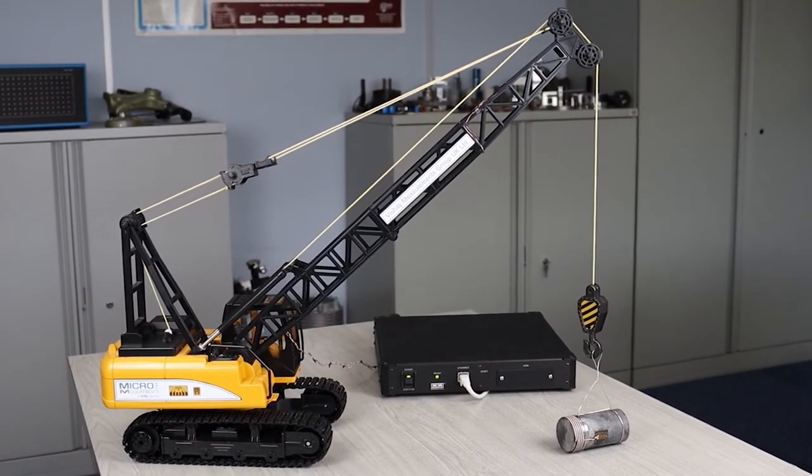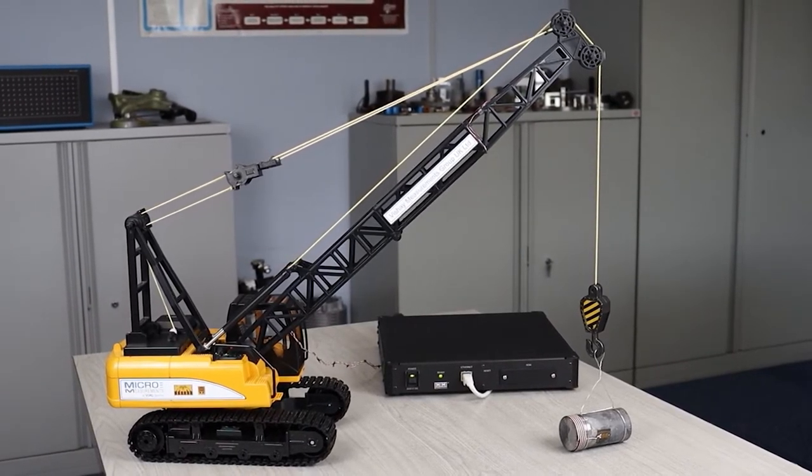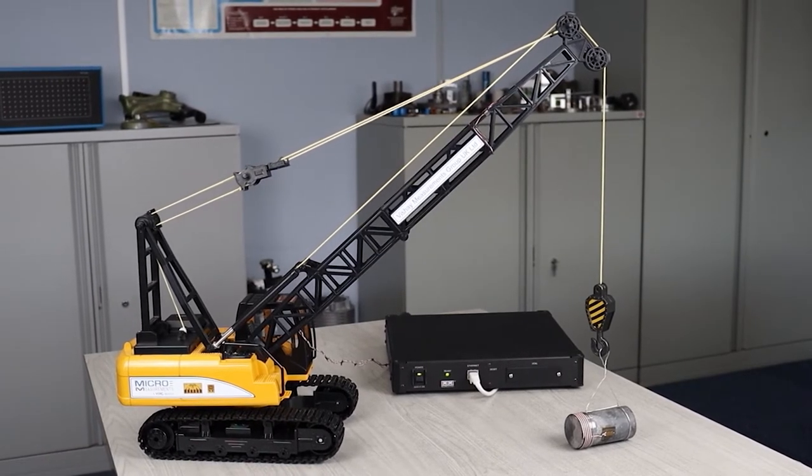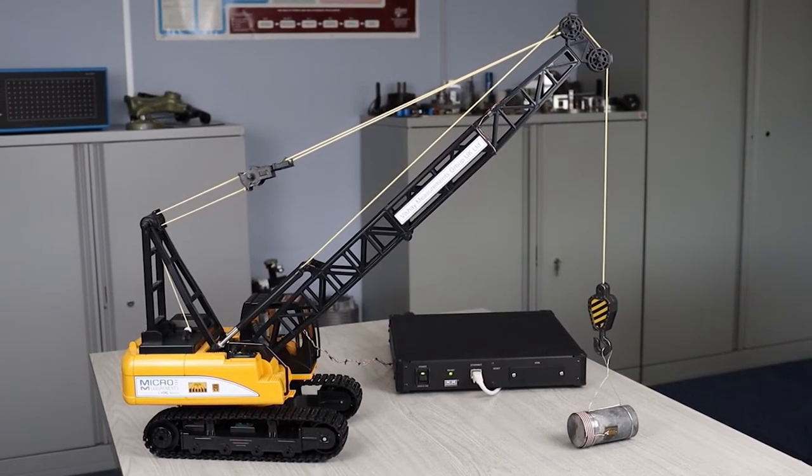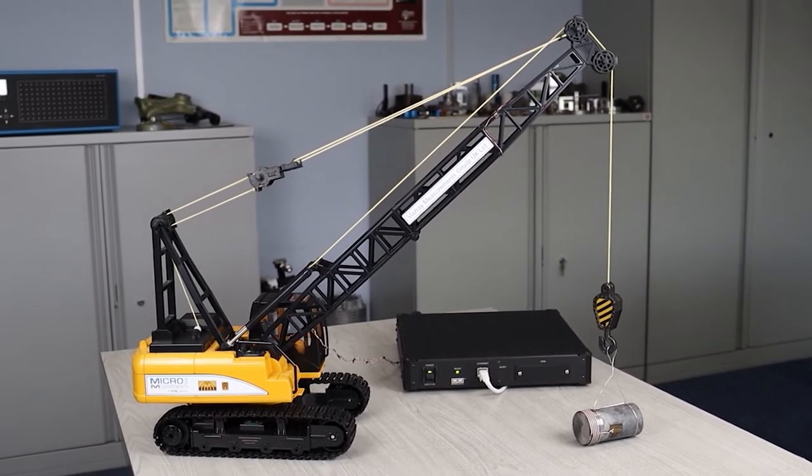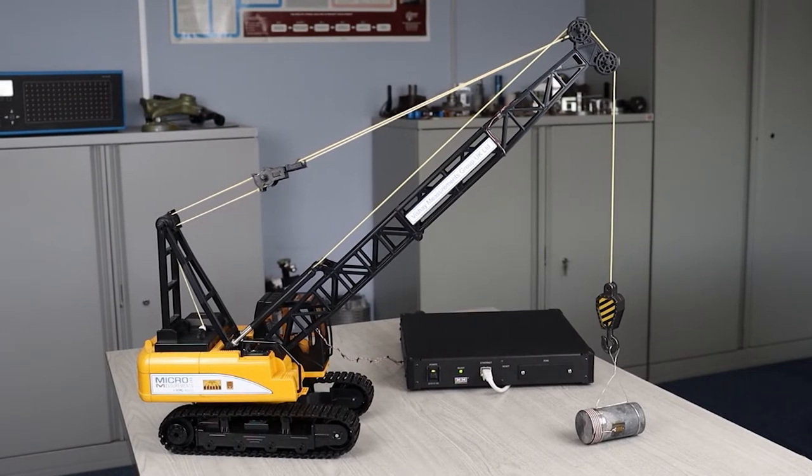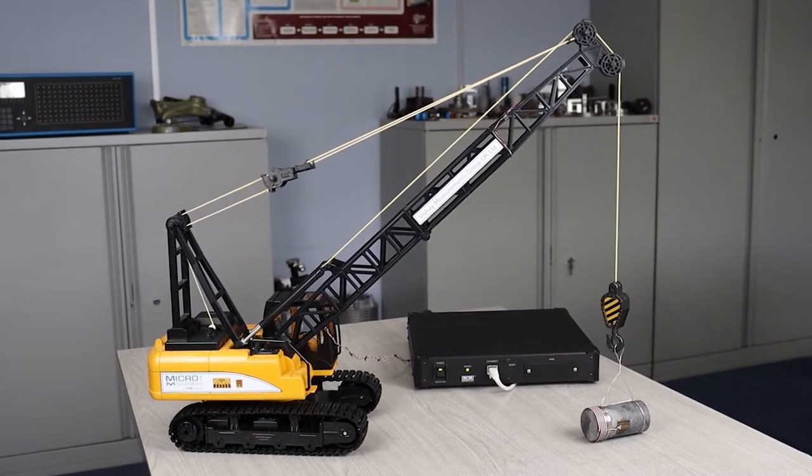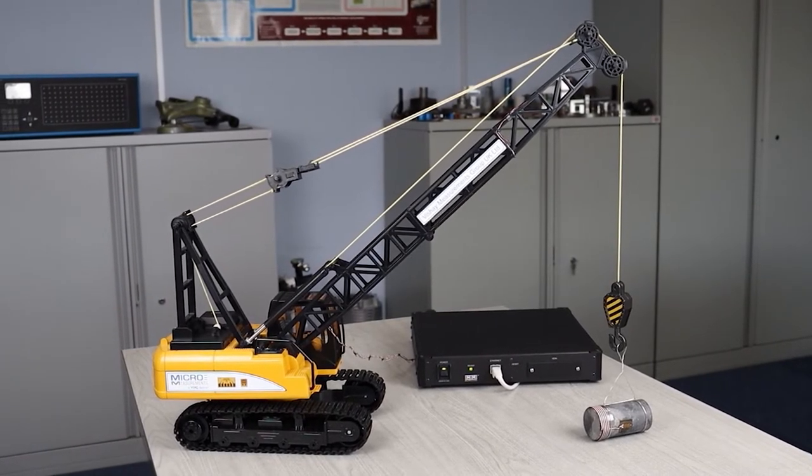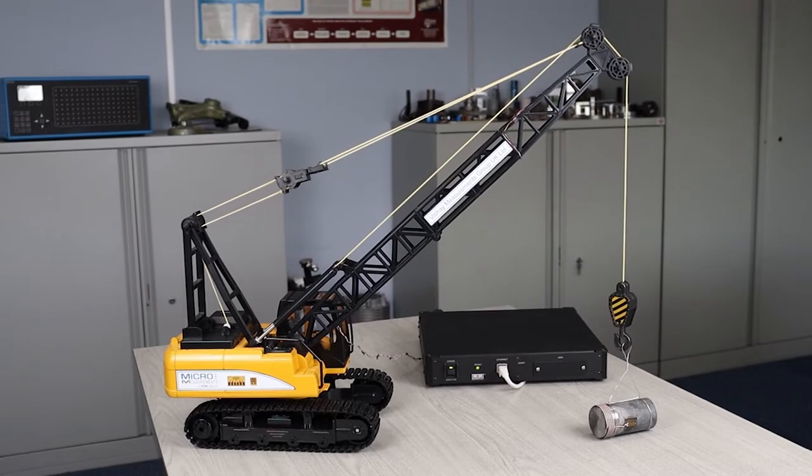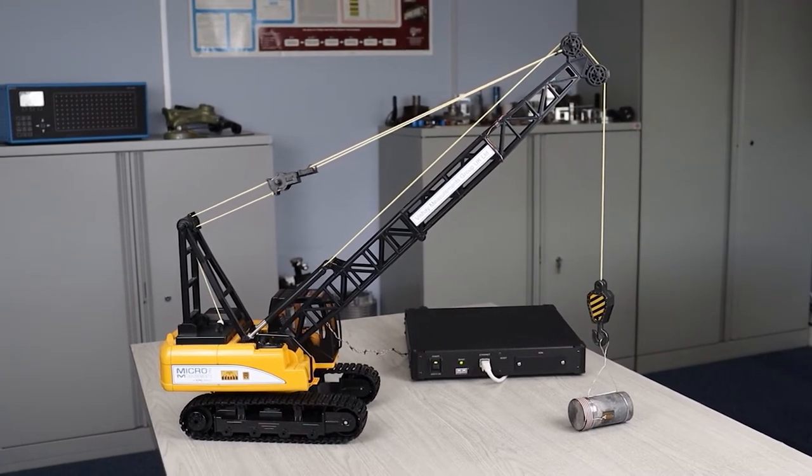You may also have a load cell in line with the hook to look at the ultimate load on the hook itself, and that's very common, often using high resistance strain gauges because they are battery powered. It's very difficult to run a wire to that load cell.